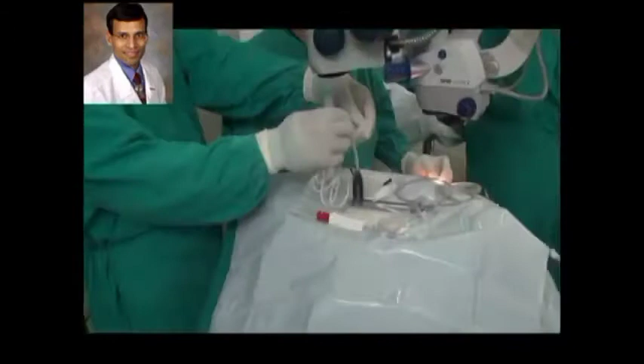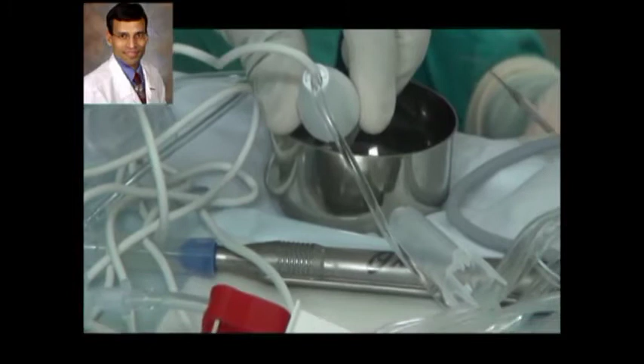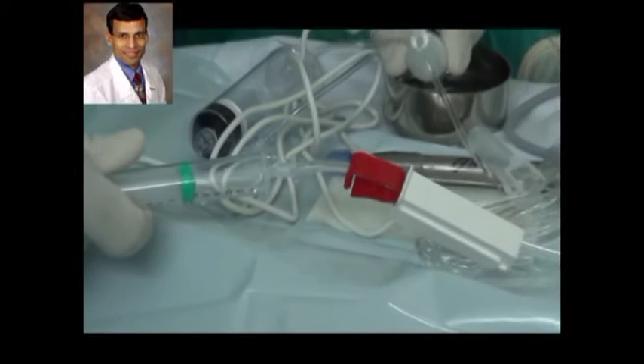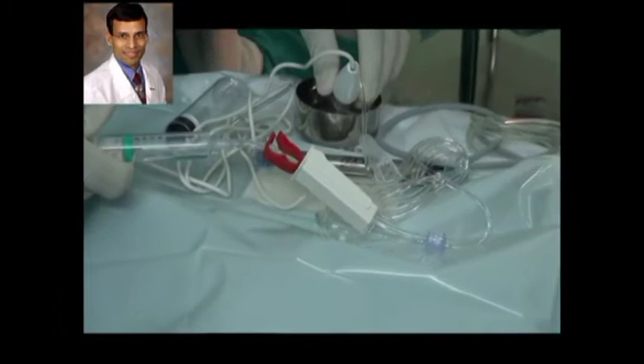So as you can see here, the disposable handpiece has an electrical wire that is attached to the console, and it also has a tube coming out. Before we connect the handpiece to the machine, we dip the handpiece into a bowl of fluid and then use a syringe at the other end of the tube to suck out BSS into the entire tubing. Apply suction till there is some fluid in the syringe as well, and the BSS is drawn into the tubing to fill the entire tubing with BSS and leaving no air bubbles.